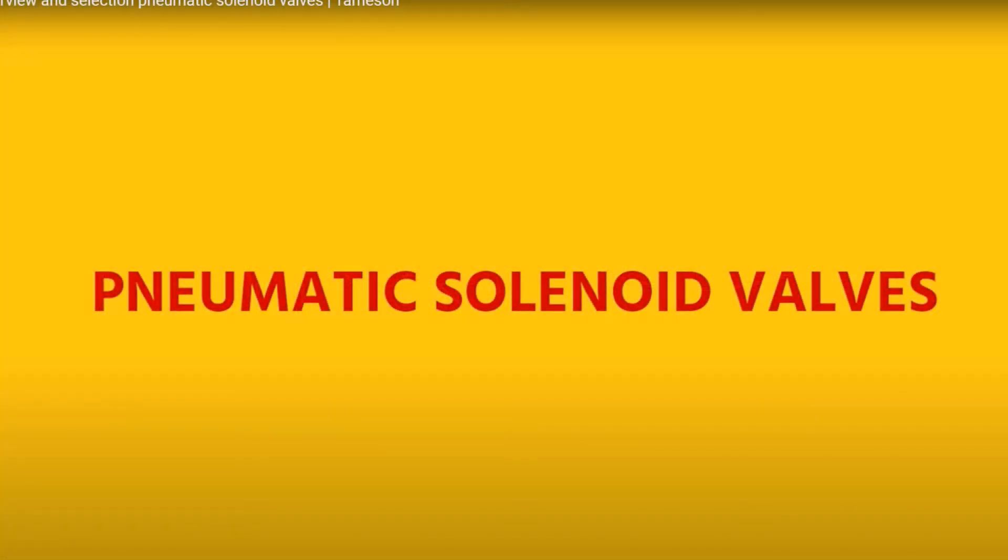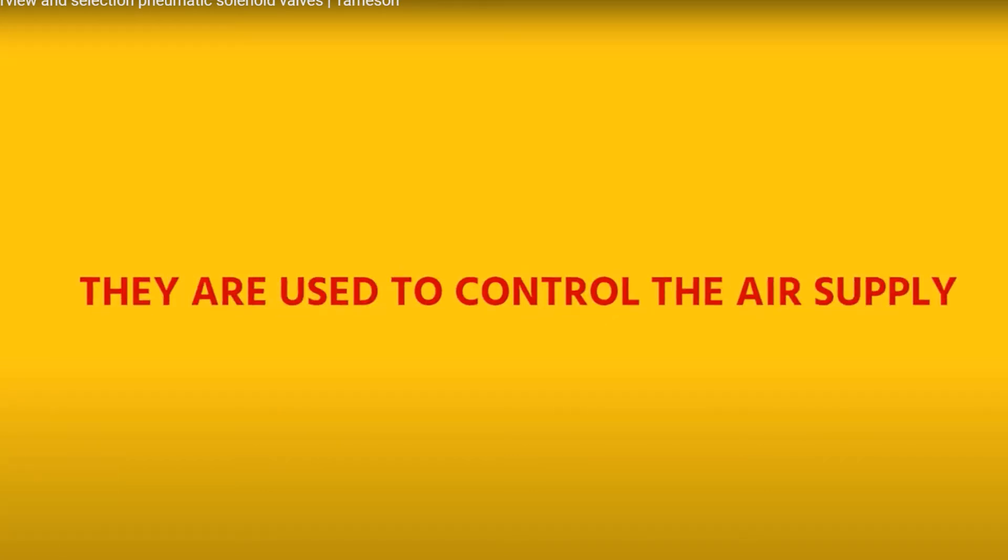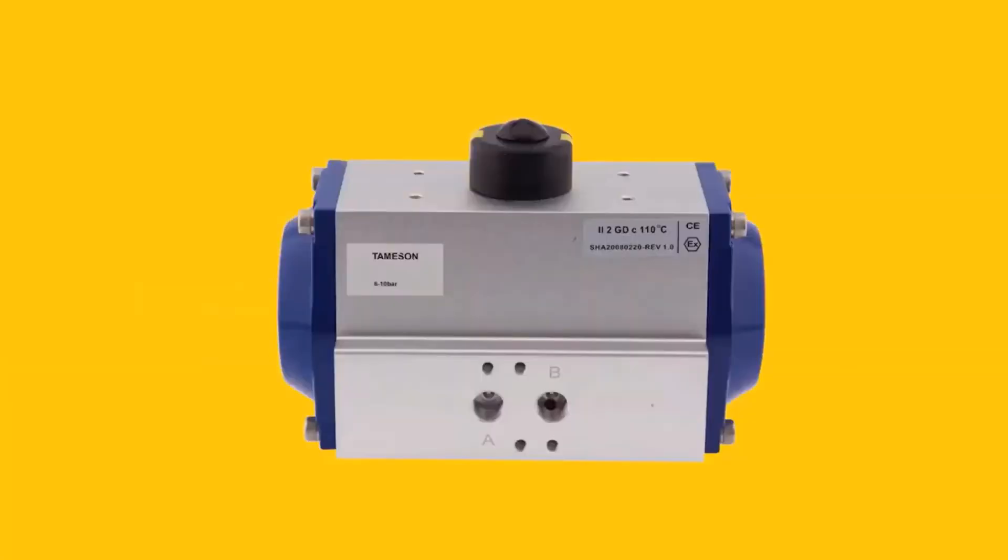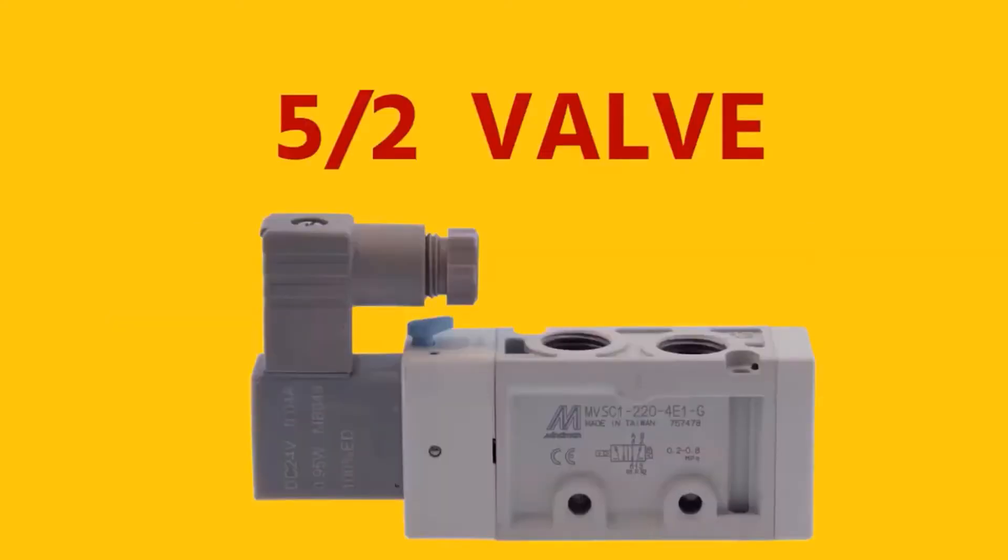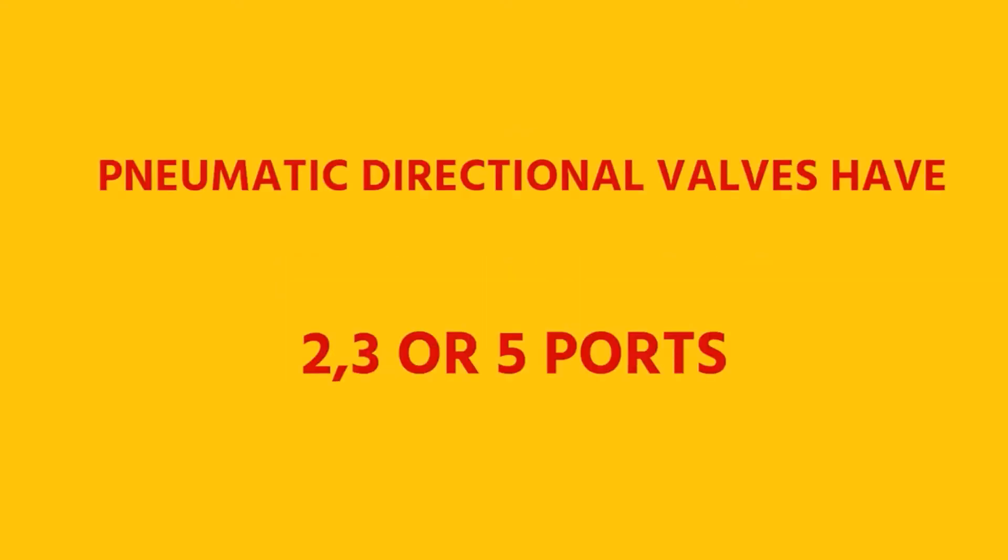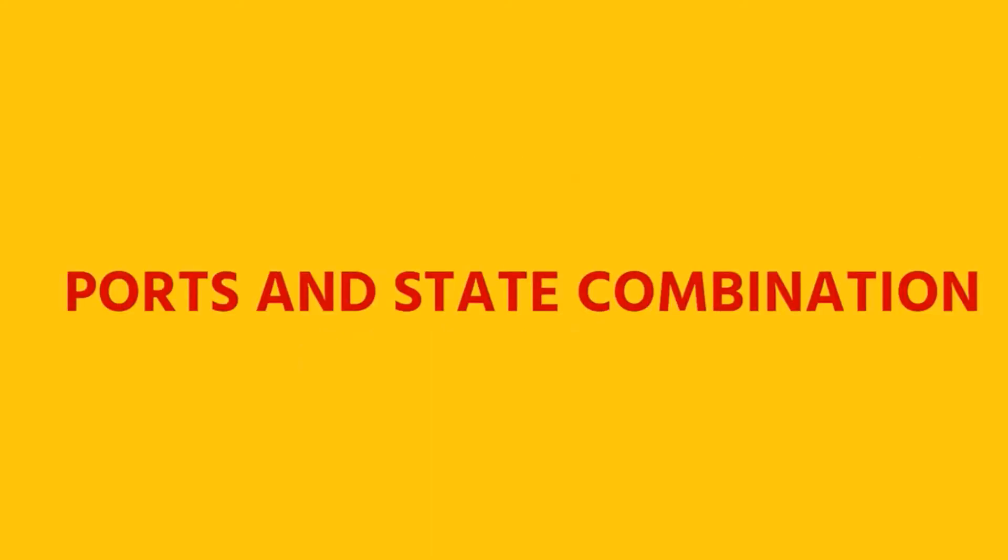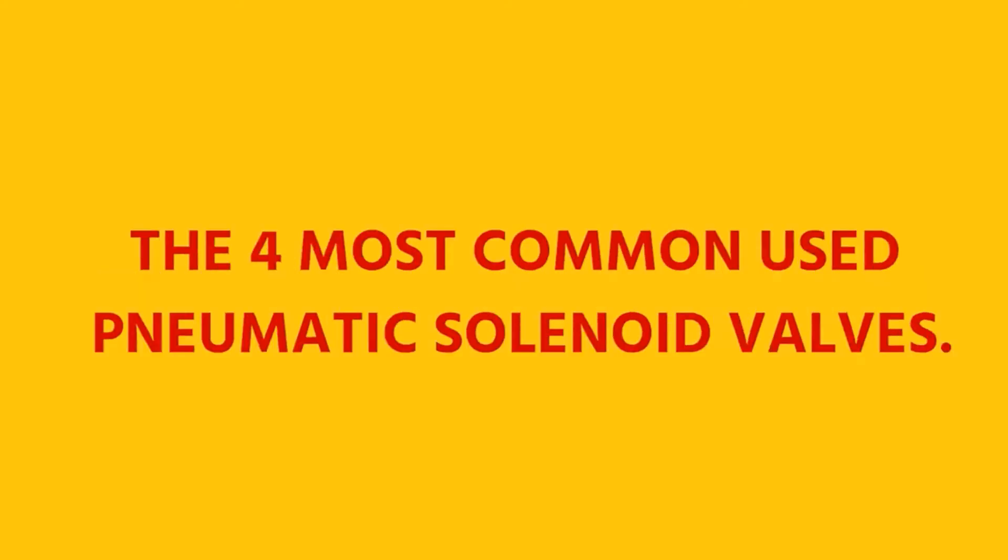Pneumatic solenoid valves are one of the most common elements in pneumatic systems. They are used to control air supply to cylinders, grippers or valve actuators. In this video, we explain how to find the correct pneumatic solenoid valve for your application. Directional valves are appointed with two numbers. The first number shows how many ports the valve has and the second number the amount of states. Directional valves usually have two, three or five ports. Selecting the correct port and state combination can be hard, so let me explain the four most common used pneumatic solenoid valves.